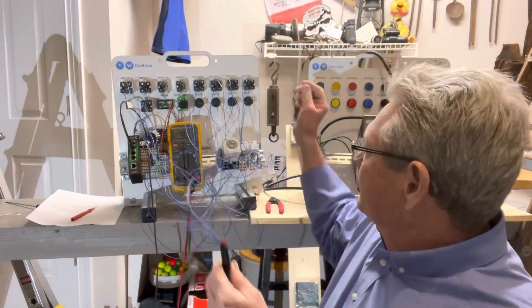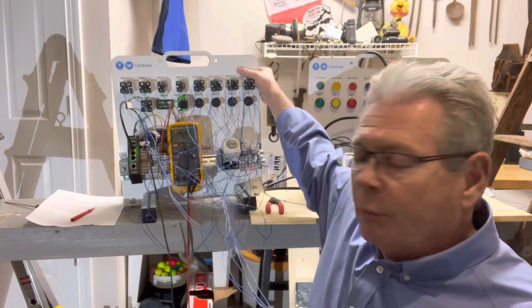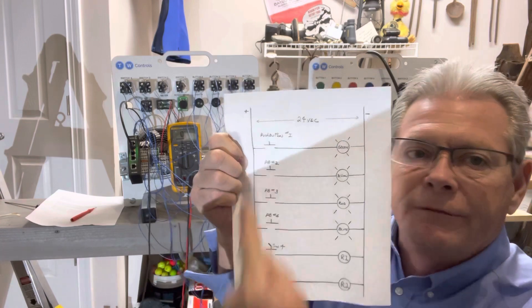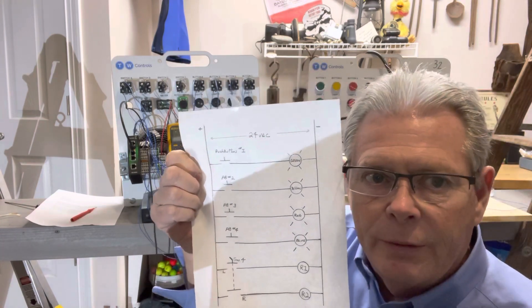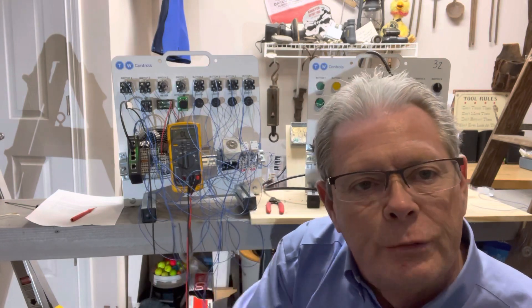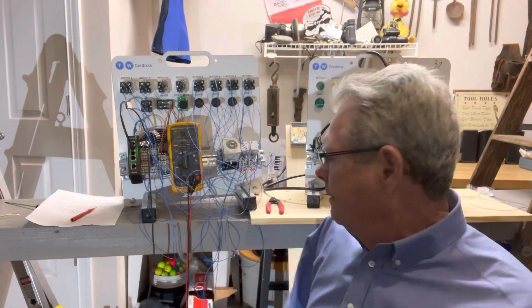Now we've got OL. If we look at our print, all these are open switches. If they're all open, we should have OL. We do. So that checks out. Infinity is a good reading if that's what you expect.